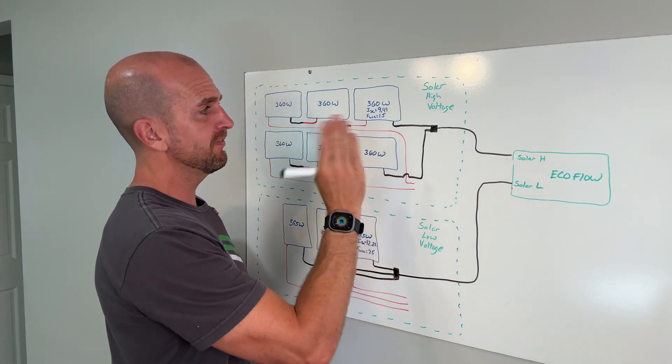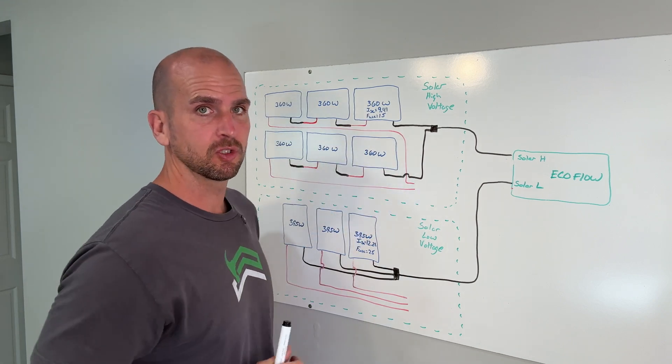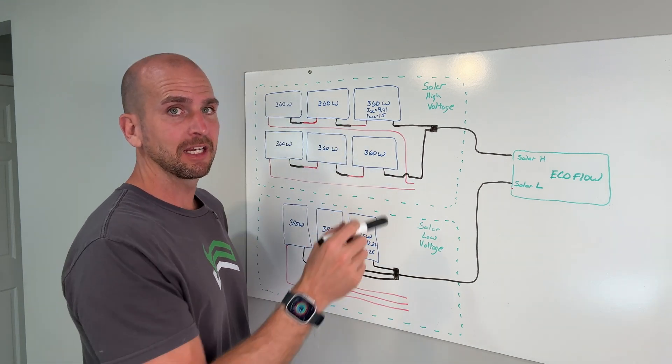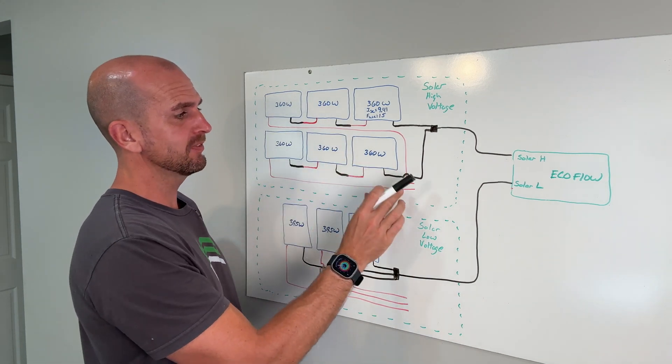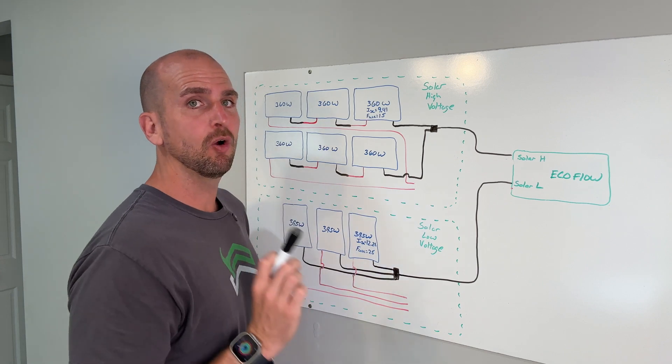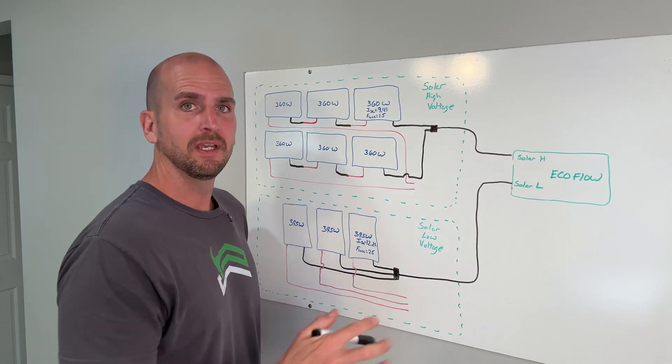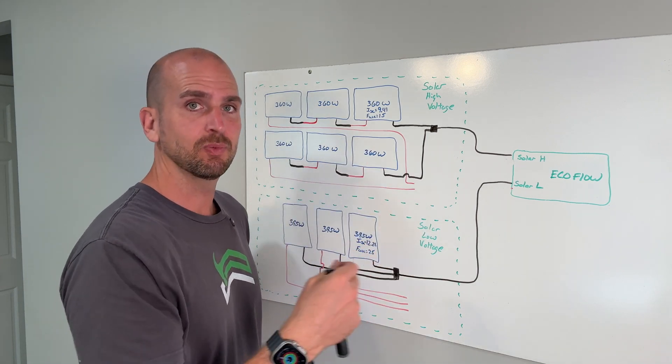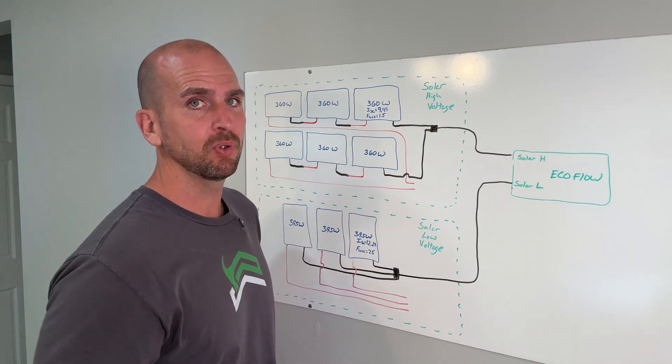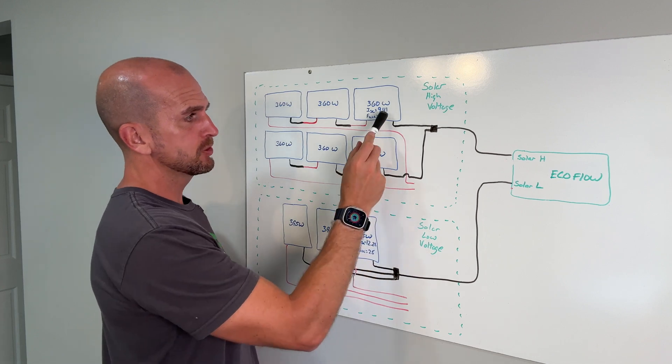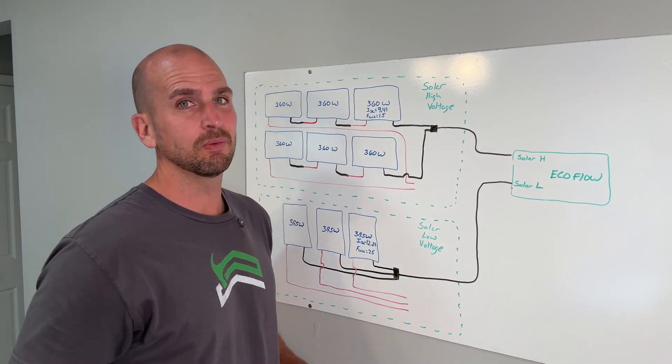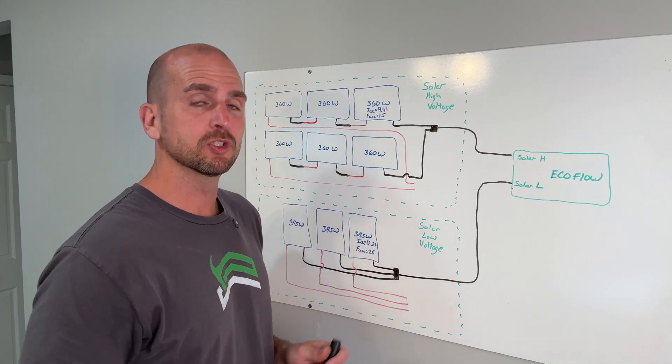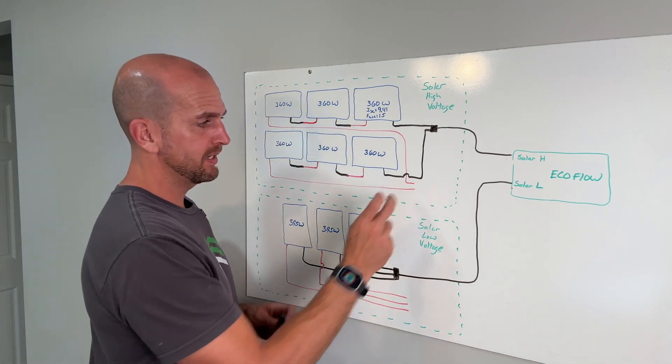If I had a failure, if I had a short circuit failure that current might be looking for the path of least resistance and we do not want to overload any one of those branches with that 18.82 amps which we know 15 amps is what it would be rated for. So we must put a fuse right there.